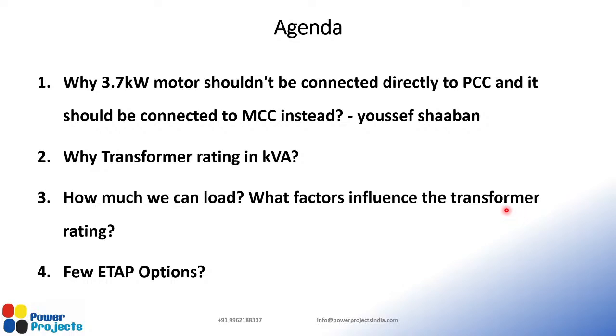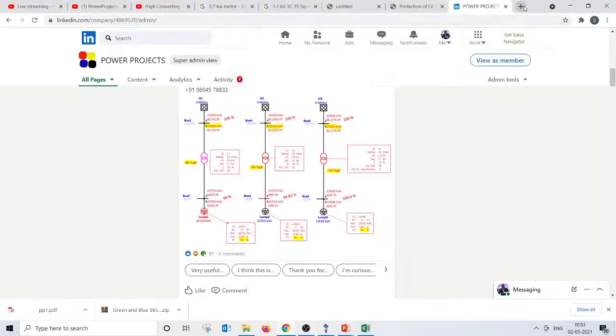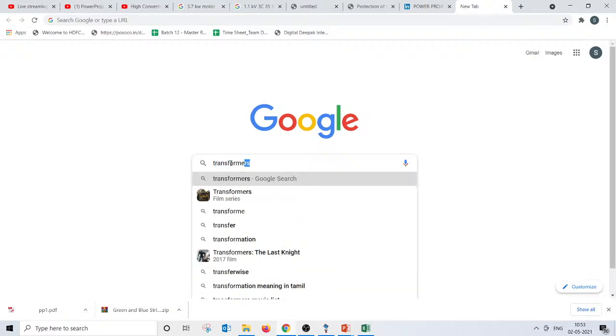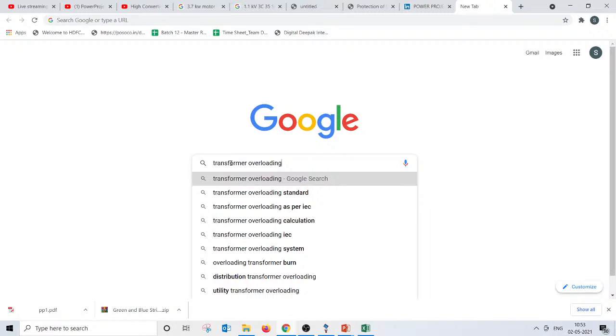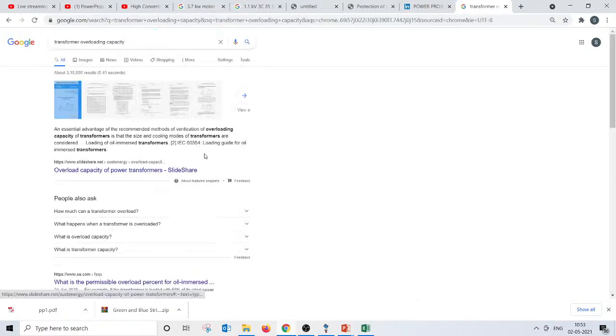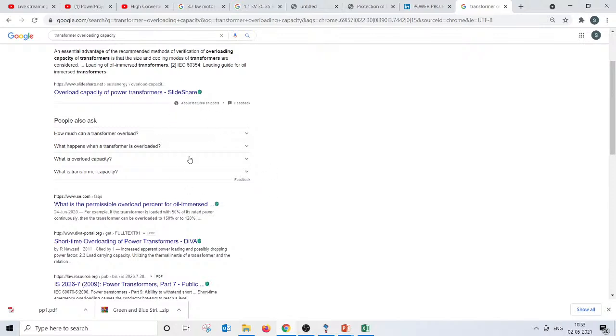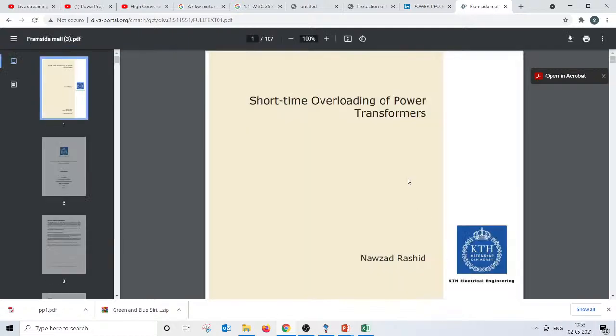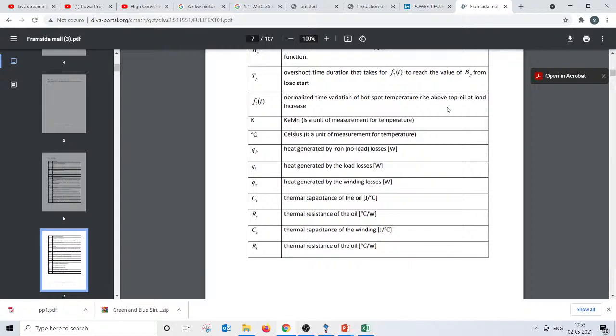And I also request you to read something more on transformer overloading, because transformers are capable of even loading up to 200 percent, right? Please go through the standard IEC 60076 again, to see what loading or overloading of the transformer is allowed. Your transformer can withstand the short circuit current itself for 2 seconds, which means it can very well load up to 200% or more, right? So you can look at IEC 60076 for the loading of this transformer, and I can leave it as an exercise for you on Sunday, or we can come back next week to talk more.